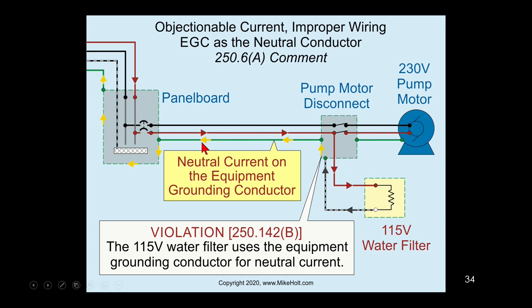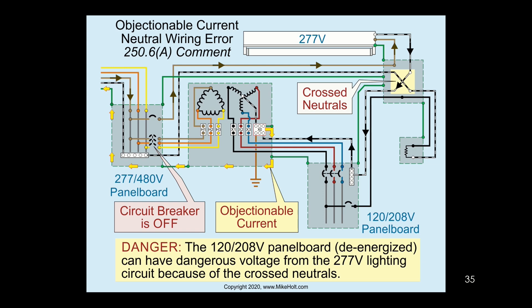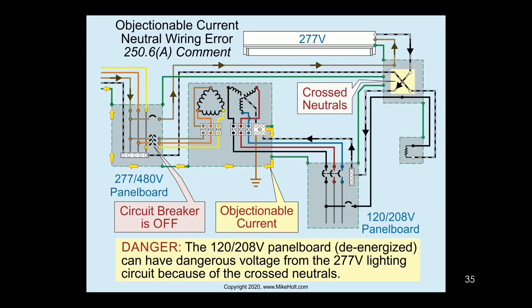Back to answering the question — making this connection causes objectionable current to travel on the equipment grounding conductor. We can put an amp meter on there and actually measure it. Now here's a scenario about as complicated as you could possibly get — this is showing you a scenario where one of our video team members' brother-in-law got killed. This shows three phases — brown, orange, and yellow — coming into a panel board with 277/480 volts coming in.